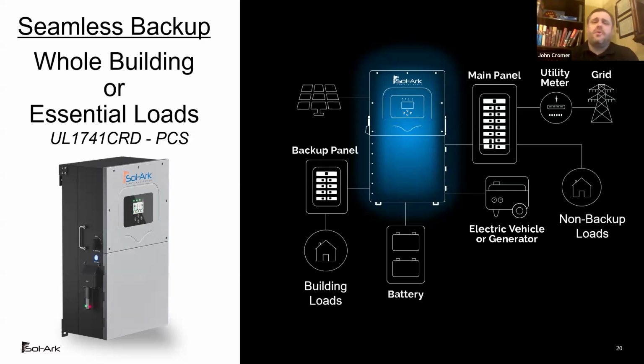And we're listed for this load side connection. Not all inverters are. There are only specific inverters. They're called UL 1741 CRD PCS listing. And all of our inverters are listed for this, but not all of our competitors are listed for this.